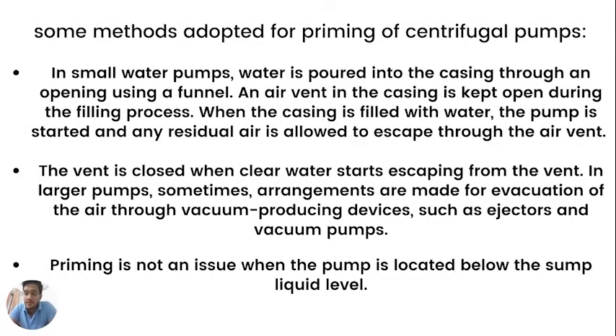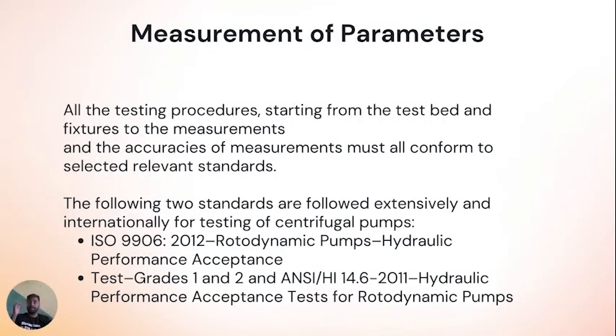Methods for priming of centrifugal pumps: for small water pumps, water is poured into the casing while the air vent is kept open; after completely filling with water, the pump starts and any residual air escapes through the air vent. For larger pumps, air is evacuated through devices such as ejectors and vacuum pumps. When the pump is located below the sump liquid level, priming is not an issue. All testing procedures — from the test bed and fixtures to measurements and accuracy — must conform to selected relevant standards such as ISO 9906:2012 test grades 1 and 2 and ANSI/HI 14.6:2011.